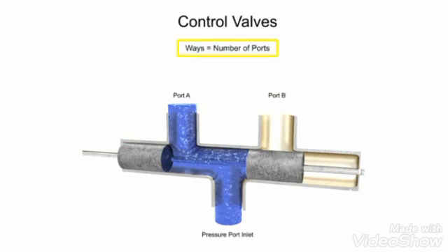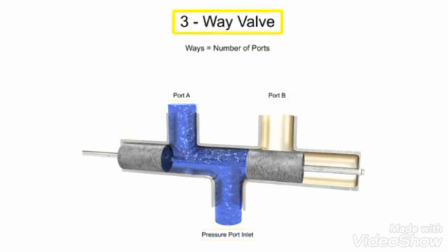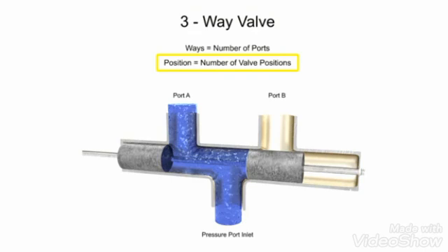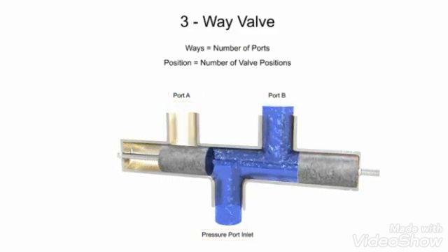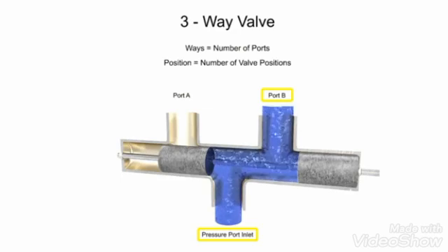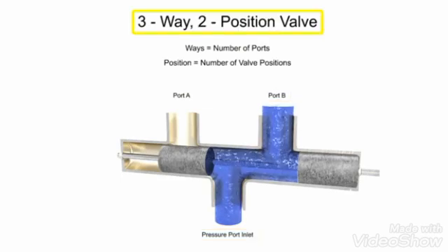A way refers to the number of active porting connections called ports. This valve has three ports, so it is a three-way valve. The term position refers to the number of discrete operating positions of the internal valve element. For this spool valve, one position allows fluid to flow from the inlet to port A, and a second position allows fluid to flow from the inlet to port B. Therefore, this is a two-position valve.